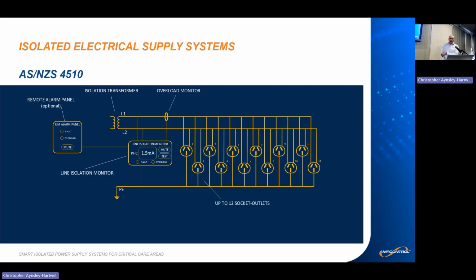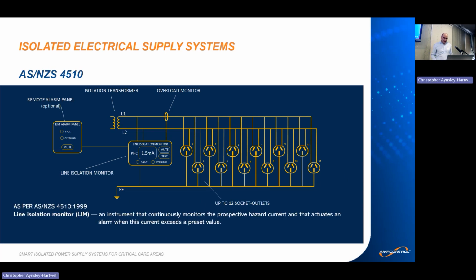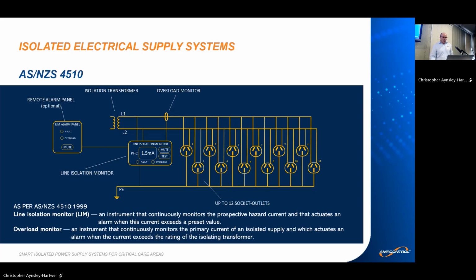The key component of any isolated electrical supply system is the isolation transformer that provides galvanic separation from the hospital electrical system and creates a system with floating earth on the secondary side. The second key component of an isolated electrical supply system is the line isolation monitor that provides continuous monitoring of prospective hazard current and triggers an alarm when the current exceeds the preset value. Overload monitoring is another essential function that monitors the load of the isolation transformer and triggers an alarm when load current exceeds the rating of the isolation transformer. And this system can also include an optional remote alarm panel to provide audible and visual alarms triggered by the line isolation monitor.